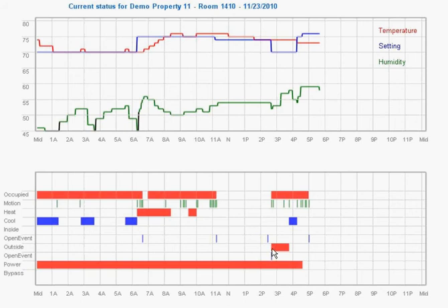As you can see, the door was opened from 2:30 until nearly 4 o'clock, standing open, the sliding glass door. The remaining bar here, the red bar, indicates that the power is turned on the thermostat on the display unit in the room, and the line below this that says bypassed, a green bar would be here indicating that the thermostat is bypassed and energy management is turned off.